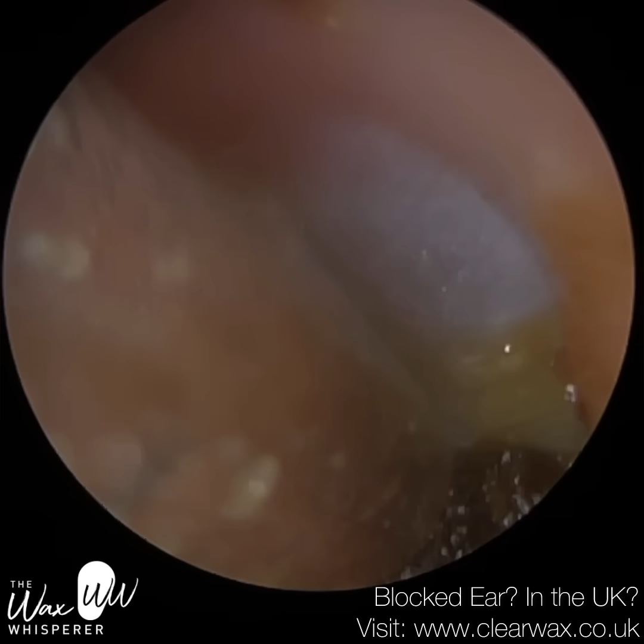And if you go around the bend in any other way, your hands are going to cross over, which means your endoscope is limited. You can't put the endoscope any further in the ear because the instrument's in the way, which then means very deep wax. You just haven't got the view with the endoscope, and then you're having to go forwards with the instrument, trying to guess how deep the wax is, and the eardrum's so far in the distance, and you're trying to remove wax which is far, far away from you visually, and you lose that depth perception.